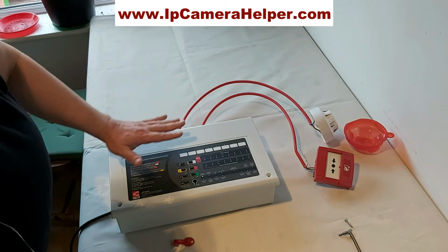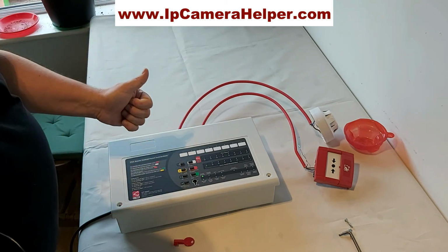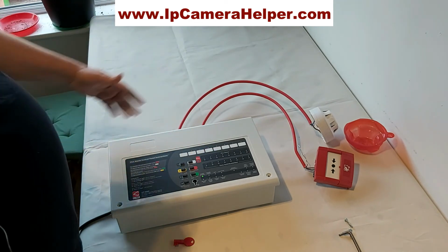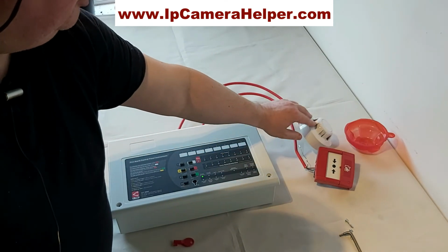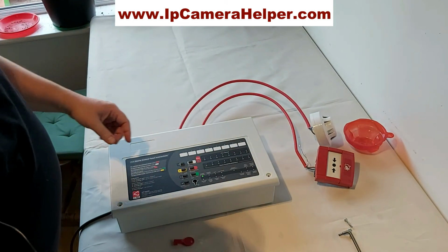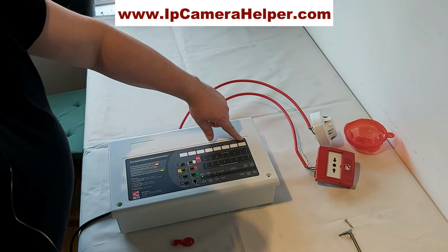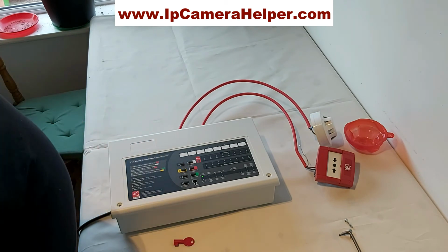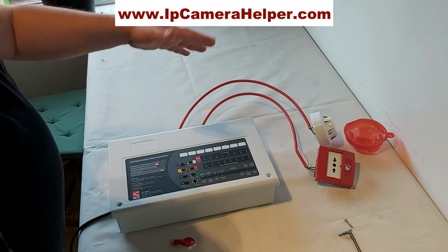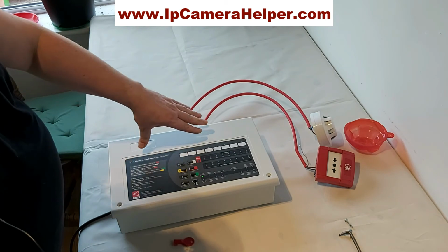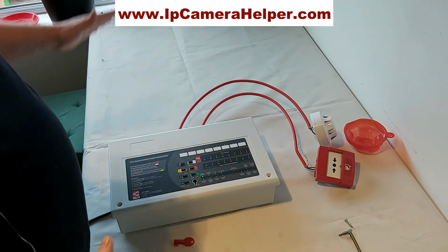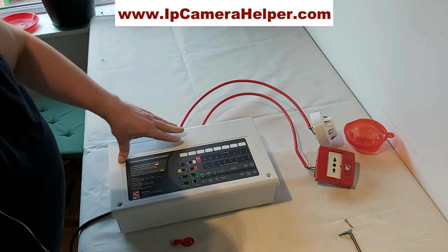So the general role of this panel is to detect faults on the system and raise an alarm when the fire condition is somewhere in the building on one of those detector lines, either a manual or automatic one. This doesn't have to be one device, it could be 20 of those devices. This panel has 2 zones, but it could be up to 8 zones if you buy a different version. So it could be quite a lot of places where those devices are, and alarm could be raised. The same with sounders. There are 4 sounder lines. They should be spread evenly around the building, so everywhere the sound level is more or less the same.